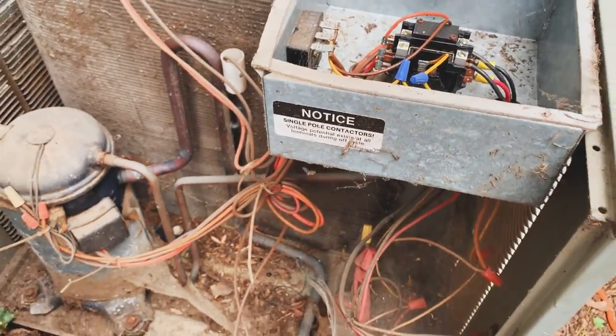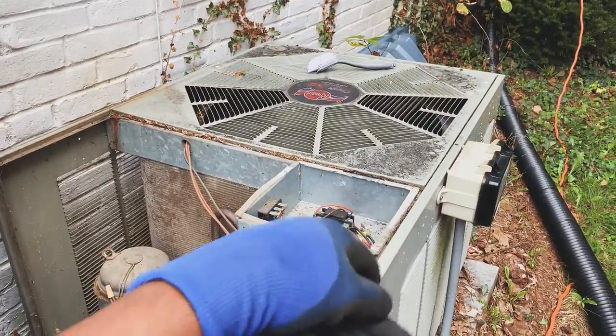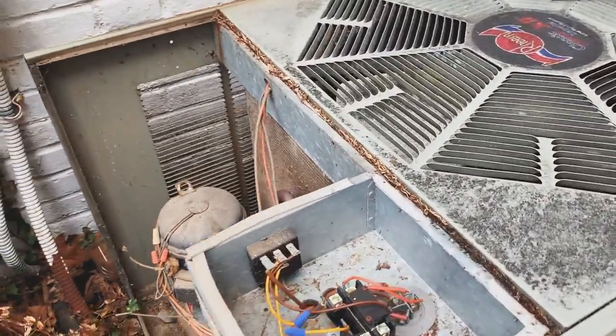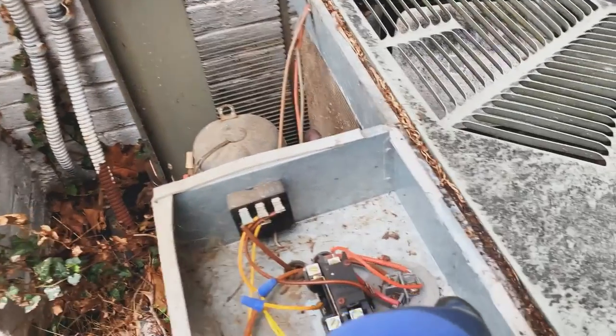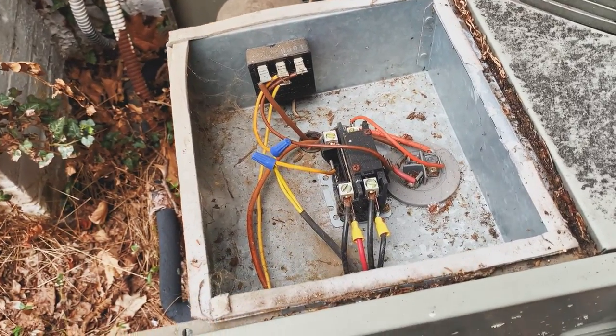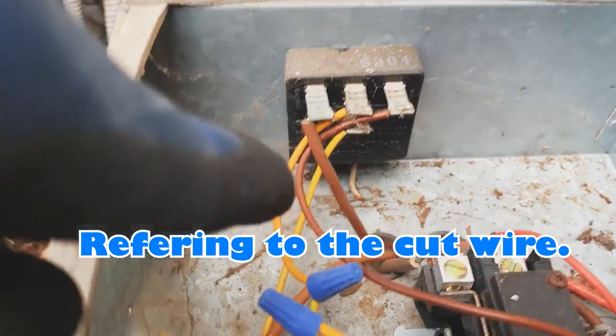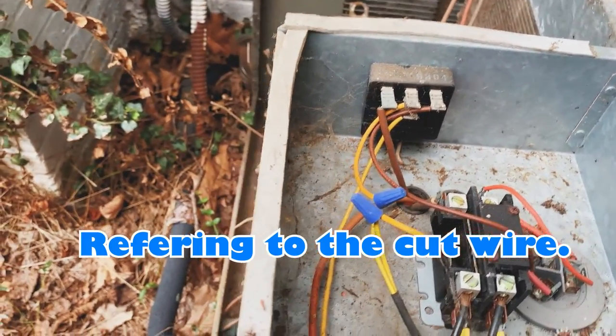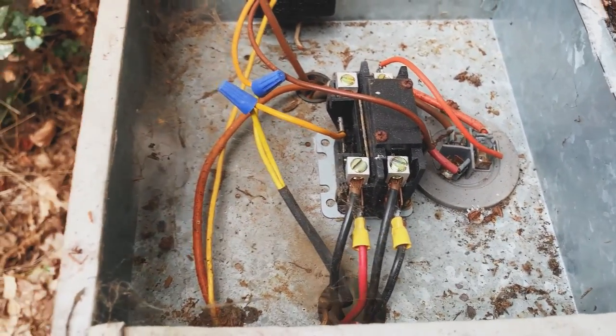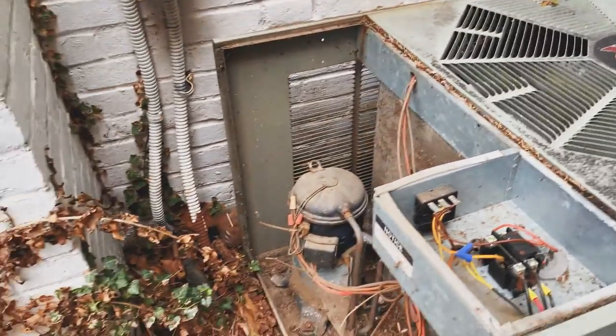it looks like it's been through some maintenance and replacement. That doesn't mean it reached its time limit and needs to be replaced. That still could be bad. The capacitor still could be bad, and the switch can also be bad. Oh, also look, see that white wire? Somebody's definitely been in here, did some snipping. Oh, we got a stink bug up in there too. Man, this is gonna be delicious.